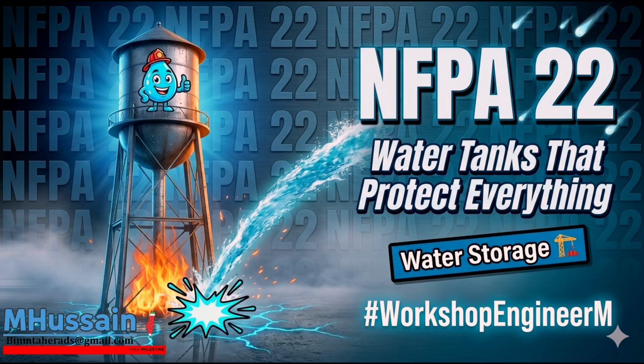Exactly. And the third reason is volume augmentation. If the city infrastructure can only deliver, say, 500 gallons per minute due to pipe friction or sizing, but your specific hazard analysis demands 1,500 gallons per minute? Right. Then the break tank makes up that massive deficit.